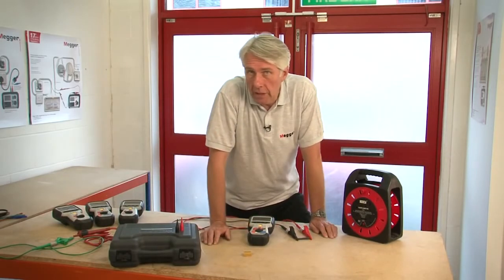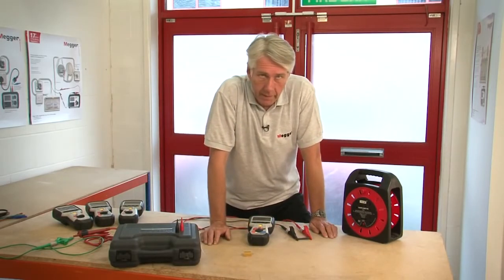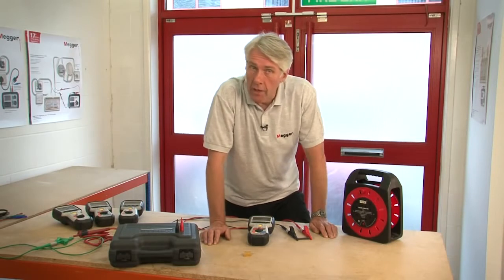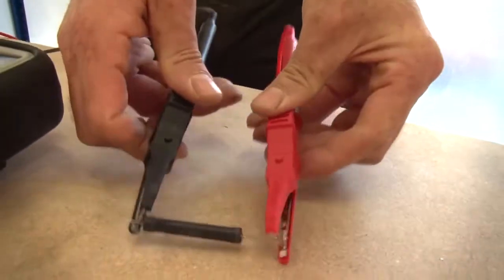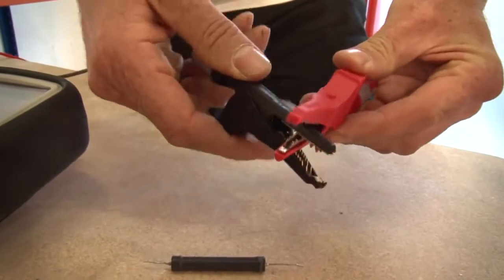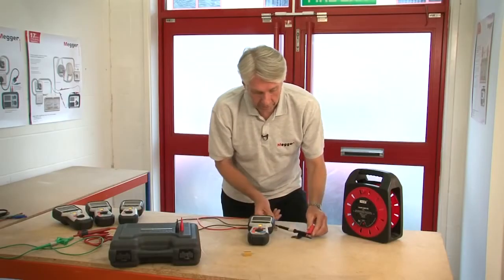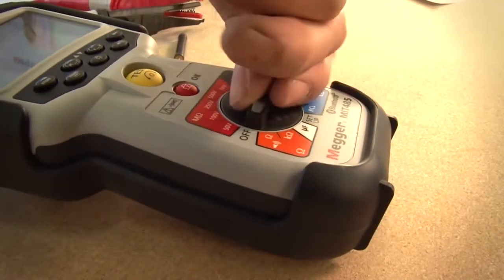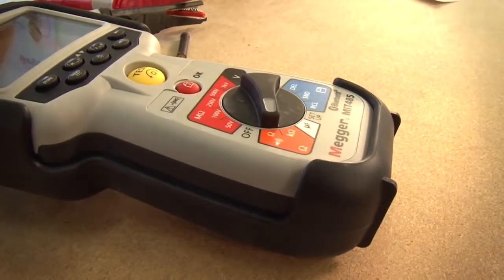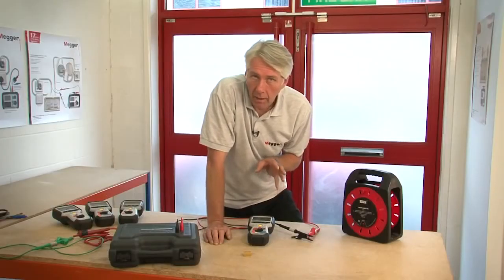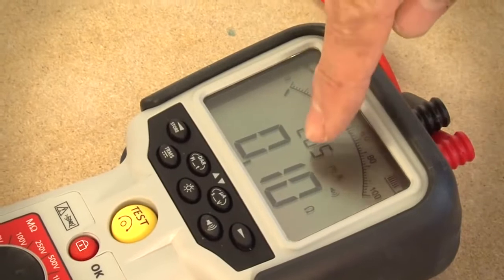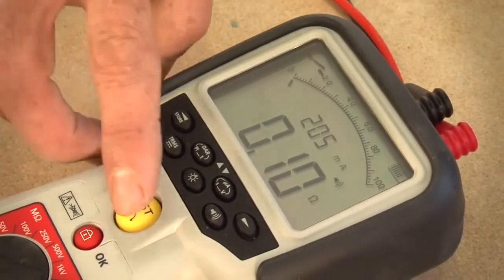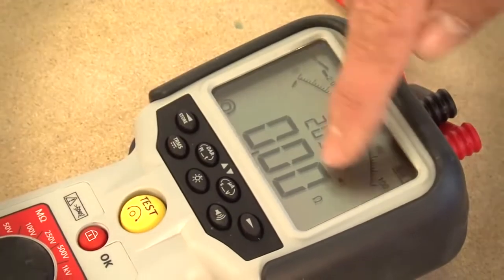Now let's look at the continuity measurement range with the buzzer. To measure continuity, you should first null out the test leads. To do that, we connect them together with a path of minimum resistance, and we select the continuity range. You can hear the buzzer because the leads are connected together. So we can see a reading of 0.01, which is the resistance of the leads, but if we press the test button, we'll null that out, and we can see the null symbol has appeared in the display.